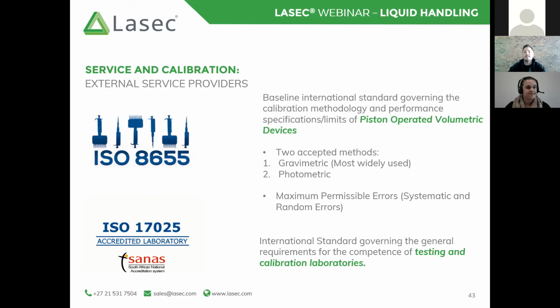Also, you get an international standard called ISO 17025, or more commonly referred to as SANAS in South Africa. All right, so although 17025 is an international standard, it's employed by many companies across the world. SANAS is South African, but it is based on the 17025 standard. Importantly, 17025 does not dictate how a calibration is going to take place. Instead, a 17025 accreditation is a laboratory accreditation, which governs the general requirements and the competency of the people in a testing and calibration laboratory.